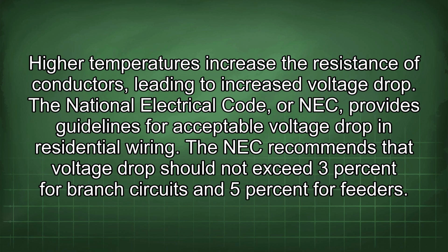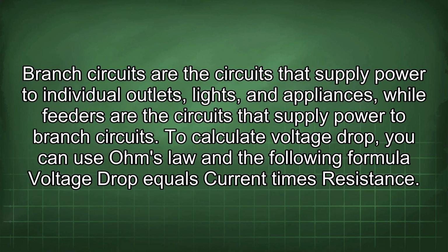The National Electrical Code, or NEC, provides guidelines for acceptable voltage drop in residential wiring. The NEC recommends that voltage drop should not exceed 3% for branch circuits and 5% for feeders. Branch circuits are the circuits that supply power to individual outlets, lights, and appliances, while feeders are the circuits that supply power to branch circuits.